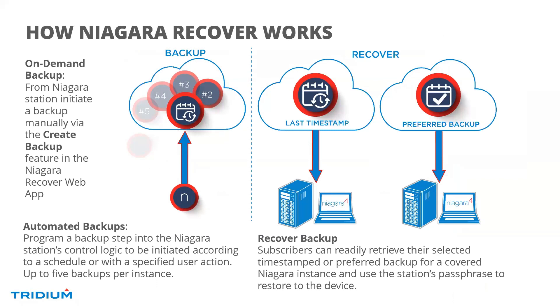You can initiate an on-demand backup from the web application by logging into the Niagara Cloud Suite and creating a backup from the web interface, or you can schedule automated backups. All are stored in the cloud — up to five, time-stamped. For recovery, you can choose the most recent backup or a preferred backup. No matter what other backups come in over time, the preferred backup will always be there. If something urgent happens on-site, log in, download that backup, and it's easily retrievable using your station's passphrase to restore it.